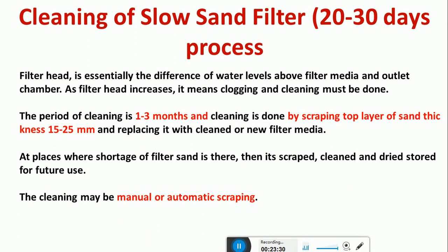So the cleaning may be manual or automatic scraping. Okay, so this is the process of cleaning of slow sand filter. So we have seen the working, construction and the cleaning of slow sand filter. So cleaning is periodically done in an interval of 20 to 30 days.